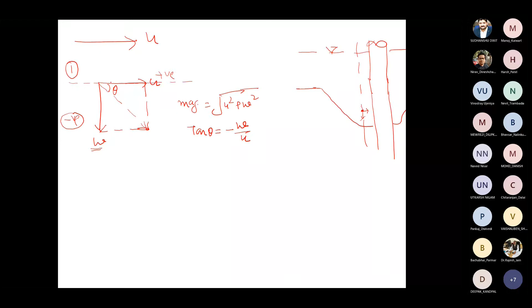Now first we talk about this value being positive, what we are getting with the ADV, and this being a negative value. If we are getting a negative value of W, then W is in the downward direction. So the movement of the flow is like this. The magnitude you calculate simply by u square plus w square. Now we talk about the angle. This angle is theta, and that is taken with respect to this horizontal line, the horizontal plane. So tan theta will simply be equal to minus w by u. Now when we are putting the data into the Excel sheet, it records the angle with respect to this plane, in the anti-clockwise direction like this.